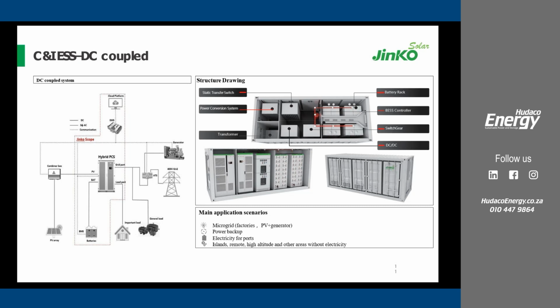So ideally that translates, assuming normal 72 cell modules, the 550s or 570s, to approximately 18 modules. 18 modules by 550 watts basically means it's less than the 50 kilowatts. So to achieve this, we need to parallel the different PV strings, of course, in a combiner box. Then from the combiner box, we'll have one output, which goes into the DC-DC unit.